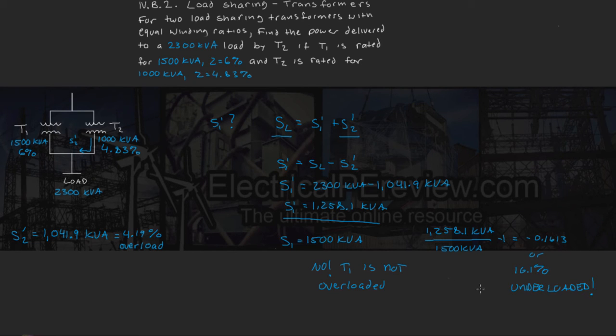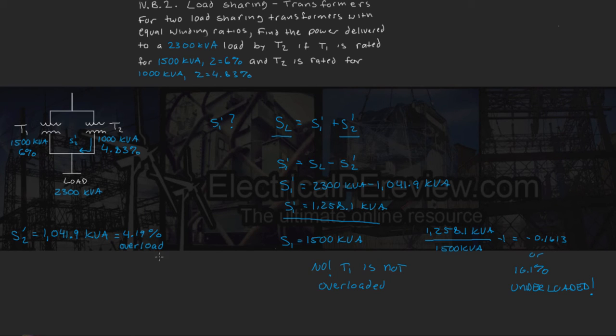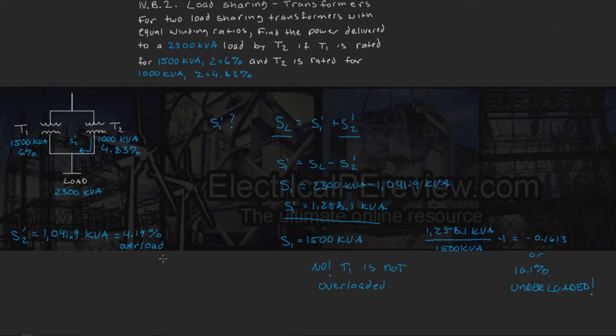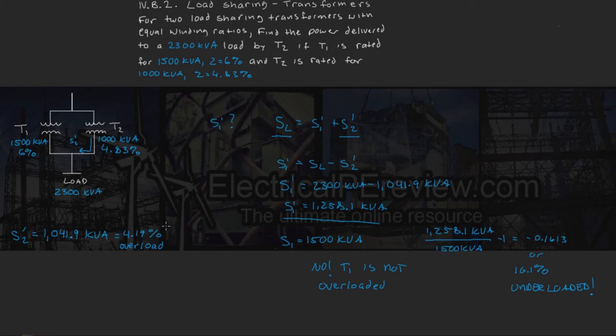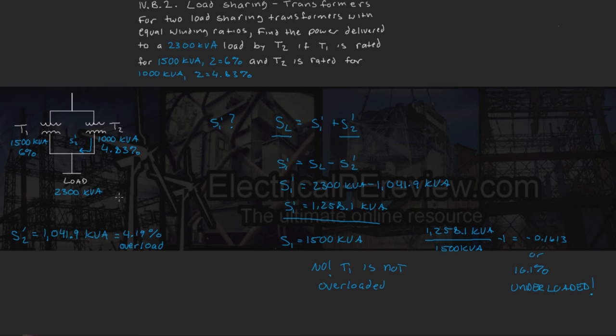Now obviously we would not operate under these conditions because doing so would stress out transformer 2 and would cause it to run at conditions rated much higher than what it was designed for. Unless, of course, the manufacturer specified that this transformer specifically can be overloaded by a percent more than 4.19% for a given time longer than what we would have it power the load to. But, of course, that would go into the actual engineering designs of the problem.